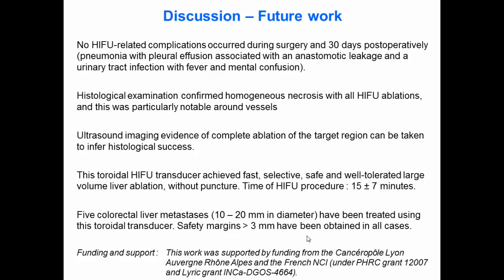You didn't monitor during the ultrasound? We cannot see anything in ultrasound images during HIFU ablation because there are interferences between the HIFU beam and the ultrasound imaging beam. But right after the ablation, since the temperature has increased up to boiling, we observed some bright echoes at the location of the ablation. But then the tissues cooled down to 37 degrees. And at this time, about 2 to 5 minutes after the ablation, we can observe the images I showed you with the hypoechoic zone corresponding to the ablation.